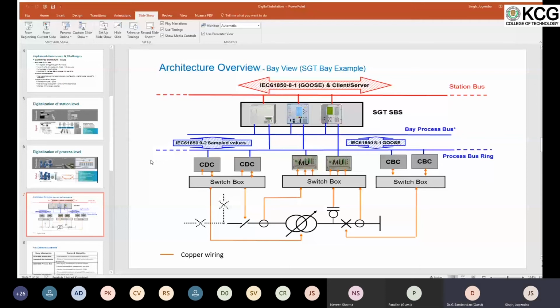I did a cost comparison back in 2005. At that time, instead of fully digital substation, we used the primary plant as conventional, and substation automation and relays as digital communication. That was quite a cost saving. You save on the copper cables, and you save on installation time, which reduces.